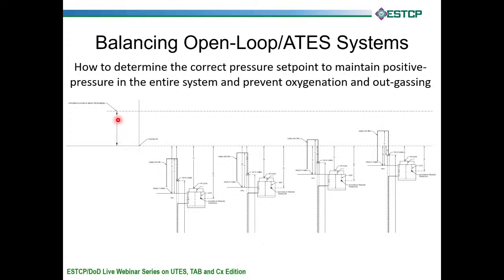But we know the elevation of our highest pipe in the system, and we want to keep 5 psi up here to keep our system from going to negative pressure, to prevent oxygenation of the water and outgassing of dissolved oxygen, and we don't want to cause any iron fouling if we have iron in the water. So we want to keep it positively pressurized, so we can easily determine from the height of our pressure transducer to our highest pipe. We can measure that. And then we need a survey instrument such as a building level to measure the elevation difference between these two.